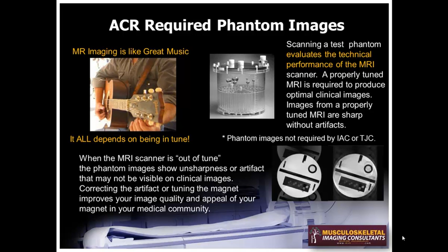A properly tuned MRI is required to produce optimal clinical images, and images from a properly tuned MRI are sharp and without artifact. To the lower right, you see scans of Phantoms with artifacts. On the left, there's a double vision type appearance with ghosting of the Phantom above and below the true Phantom. On the right, you see the unsharpness or motion type artifact created by improper tuning of the magnet. When the MR scanner is out of tune, the phantom images show unsharpness or artifact and may not be visible on the clinical images. Correcting the artifact or tuning the magnet improves your image quality and the appeal of your magnet in the medical community.